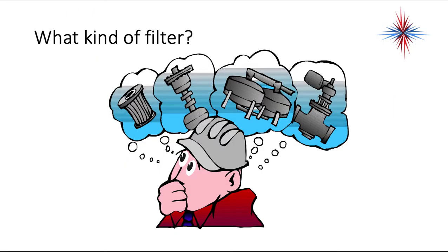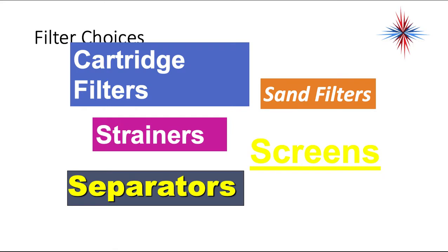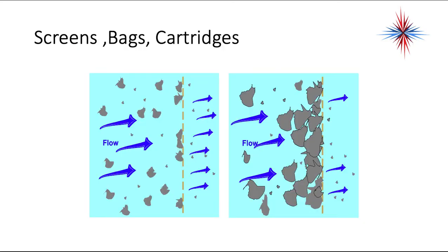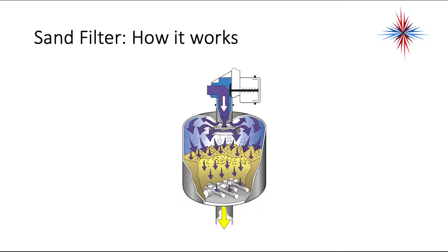For filtering we have cartridge filters, sand filters, strainers, screens, and separators. Screens, bags, and cartridges are very effective unless there's larger contamination in the fluid which can blind a barrier filter quickly, leading to excessive pressure loss and cleaning or replacement routines. The sand filter is more like what you find in a swimming pool — it relies on a bed of coarse sand media to capture contaminants on its upper surface, and to clean it, you backflush the sand or replace it.